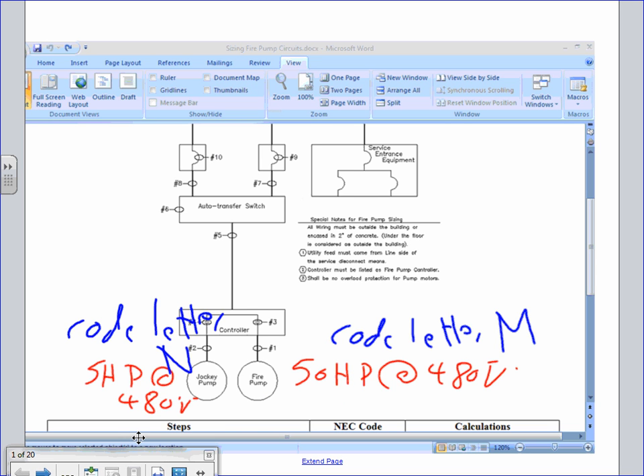I do have a 50 horsepower motor running at 480 and a 5 horsepower jockey pump running at 480, and the code letter for the fire pump is M, the code letter for the jockey pump is N. Did you hear me? That's all you need to apply these 10 things. So the question is, let's calculate these 10 things for these 2 pumps.